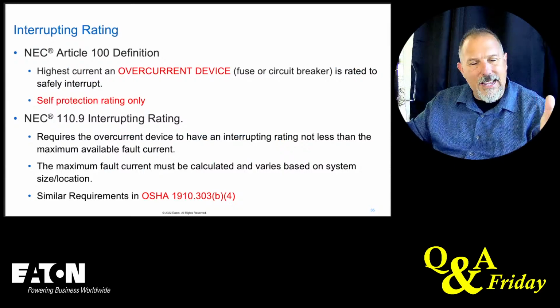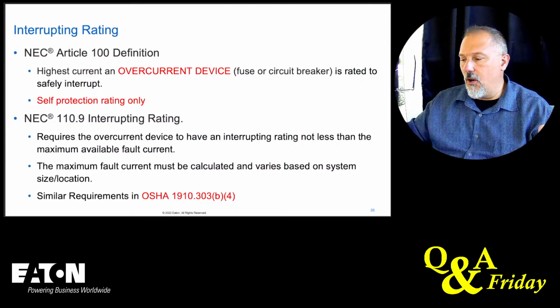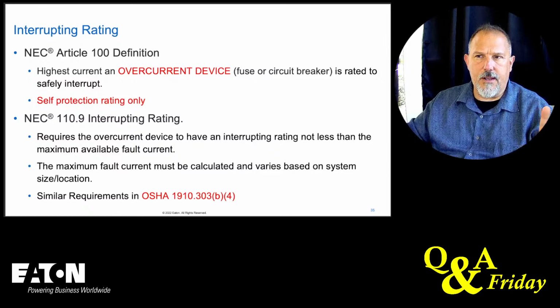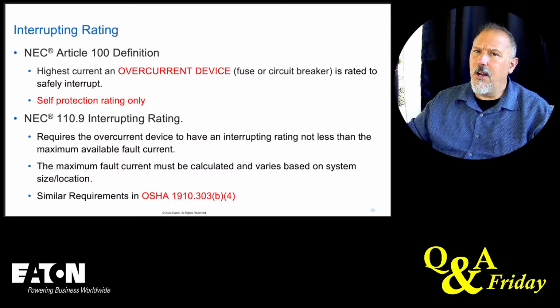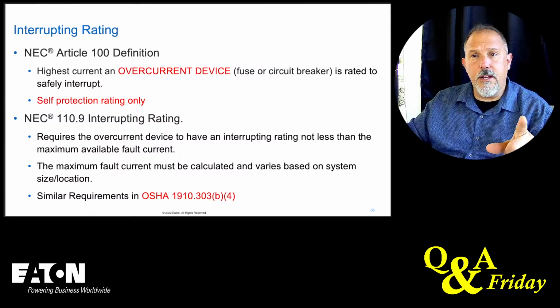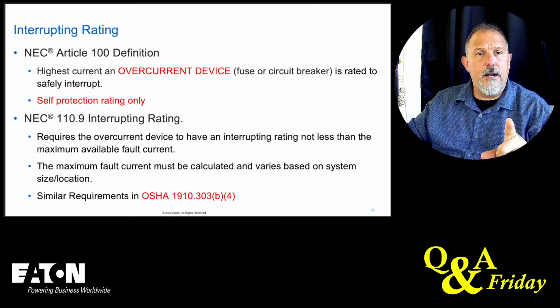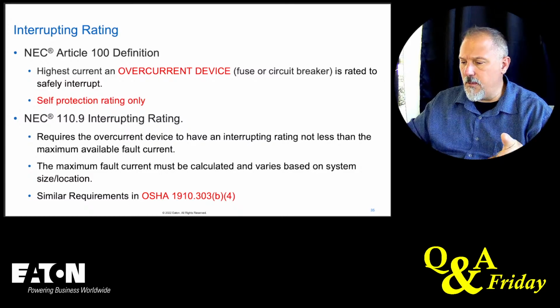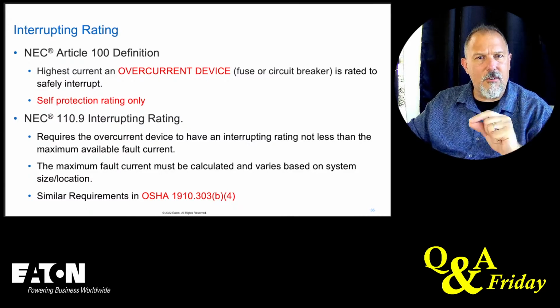It's the highest current that the overcurrent protective device, and I'm talking, it could be a fuse, it could be a circuit breaker, a molded case, insulated case, power circuit breaker, any classification of fuses. It's not necessarily, an interrupting rating could be on a switch as well that's non-fused. It's the maximum amount of current that it's rated to safely interrupt.